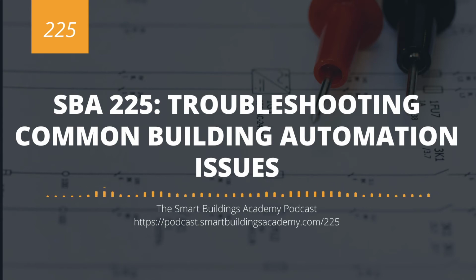Oftentimes, if I have a communication bus that has a bunch of controllers working, and then all of a sudden, after a specific controller, the communication bus just dies and there's no more controllers coming on, then I have a completely different troubleshooting path versus if I have two controllers where one of them sometimes shows up and then sometimes the other one shows up. Those are indicative of maybe a duplicate MAC address or duplicate device instance, and whichever one gets its token faster is going to be the one that shows up initially during polling. So you can start to see a couple of issues related to COM issues and protocol issues come up.